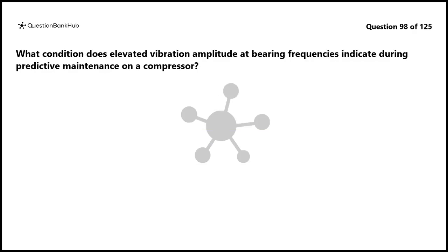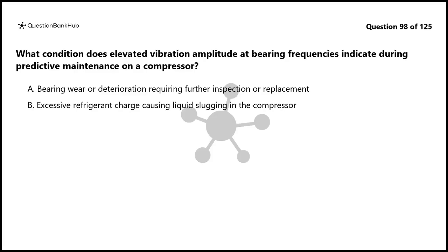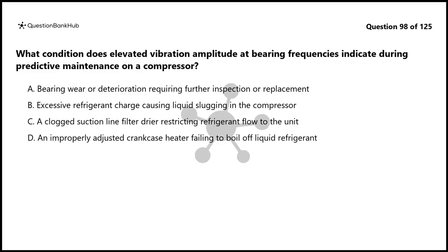Question 98. What condition does elevated vibration amplitude at bearing frequencies indicate during predictive maintenance on a compressor? A. Bearing wear or deterioration requiring further inspection or replacement. B. Excessive refrigerant charge causing liquid slugging in the compressor. C. A clogged suction line filter dryer restricting refrigerant flow to the unit. D. An improperly adjusted crankcase heater failing to boil off liquid refrigerant.